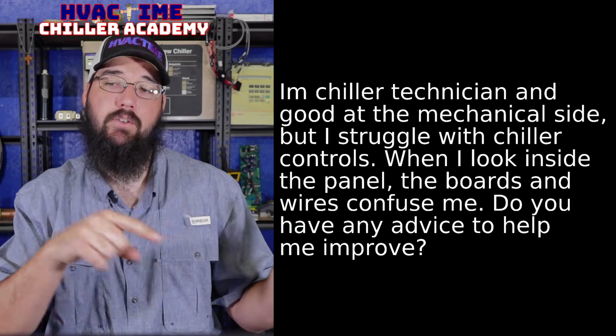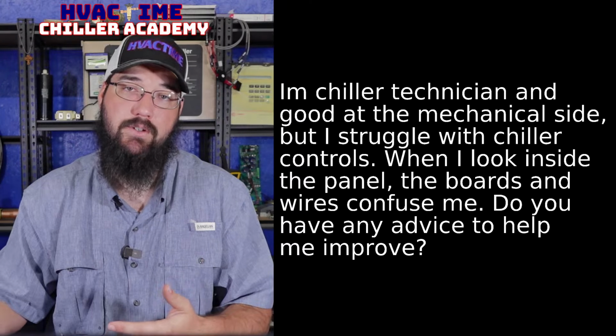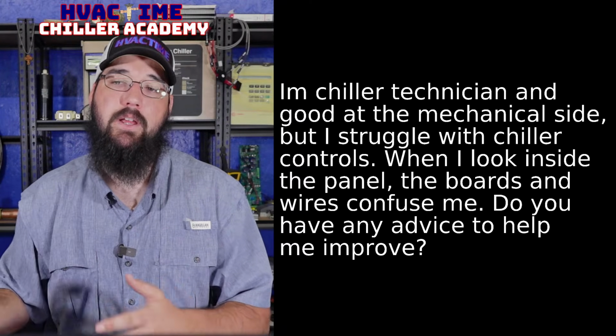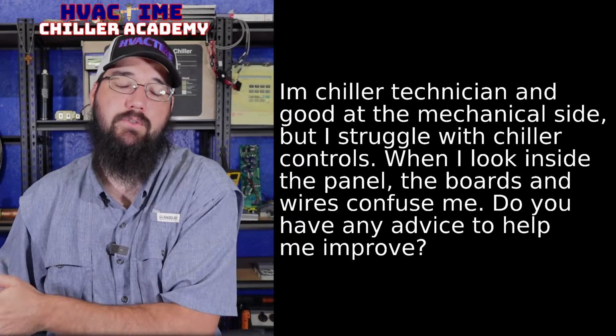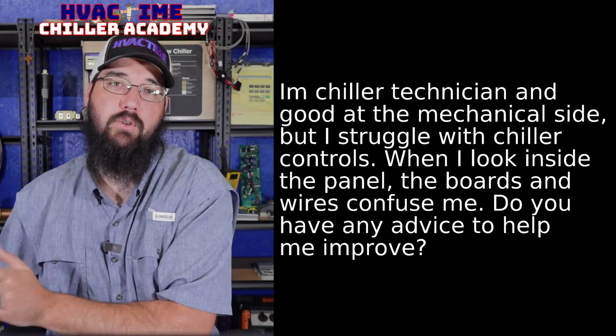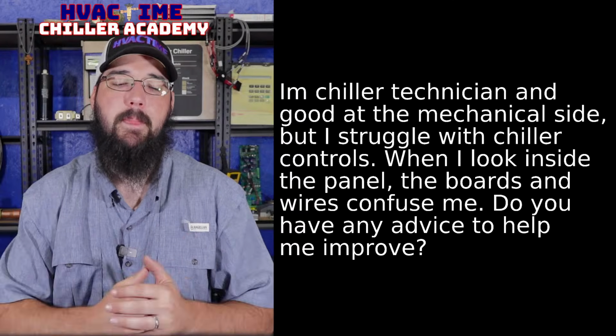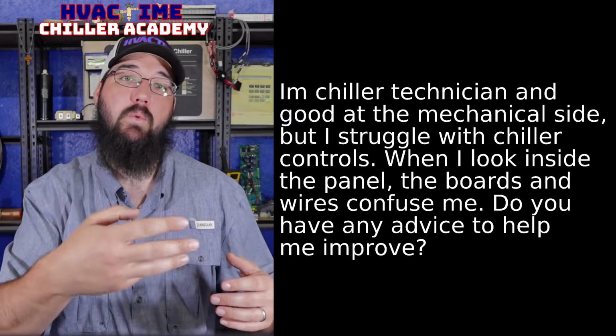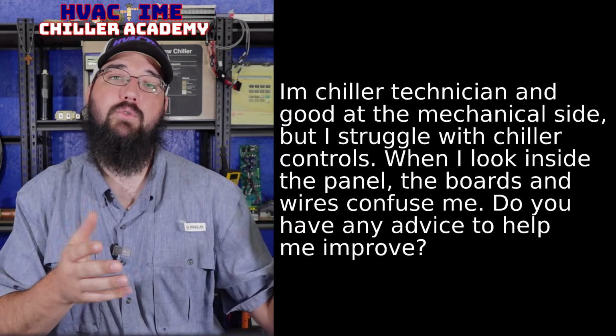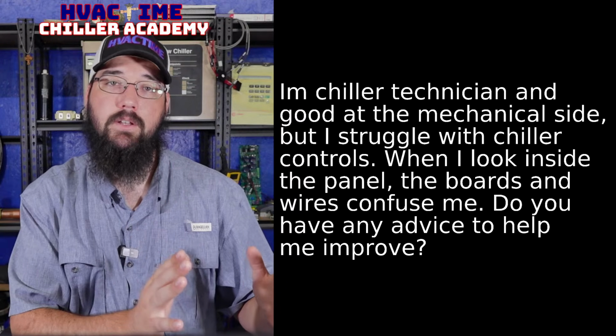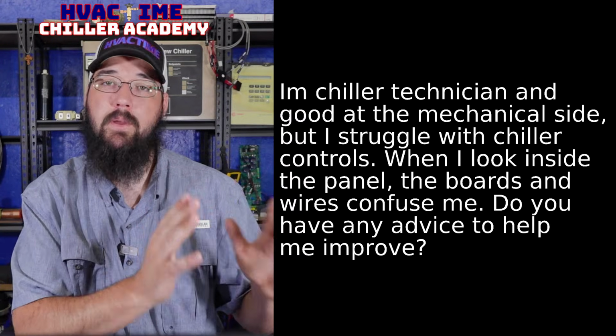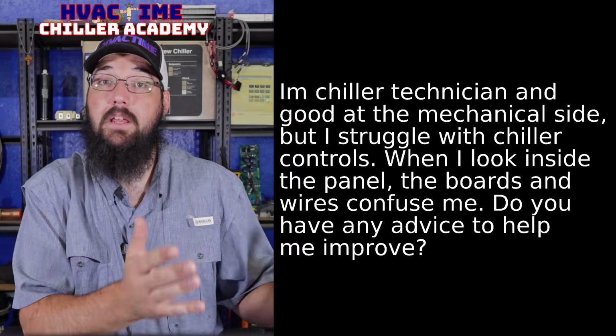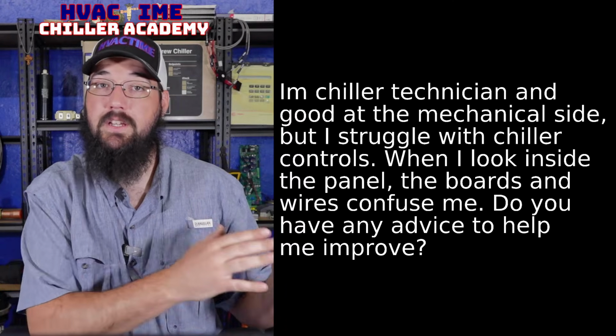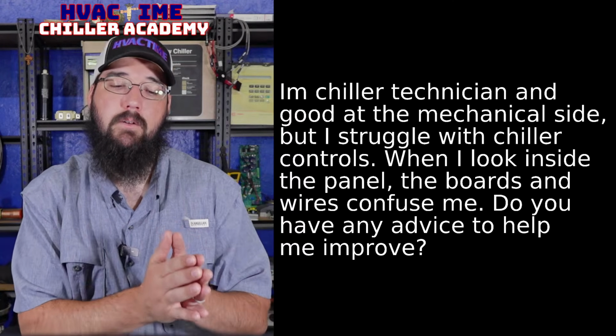And you've got to then cross-reference P2 to the legend to then have the legend explain that, okay, P2 is suction transducer for circuit 2. There you go, right? Something like that. And then I can trace those wires. And those wires will be connected to the main board, which the main board may have its own designation like MBB or just MB as an example.